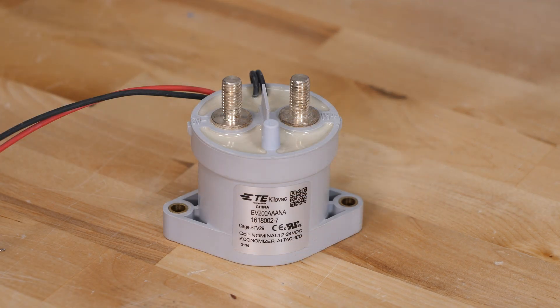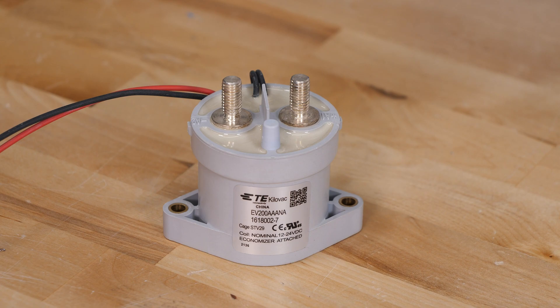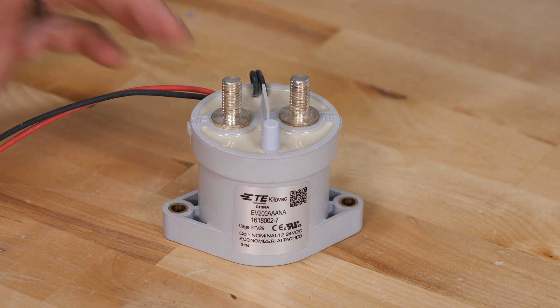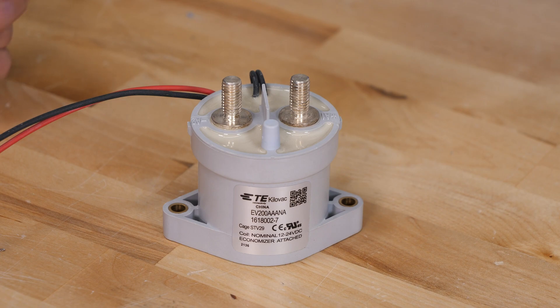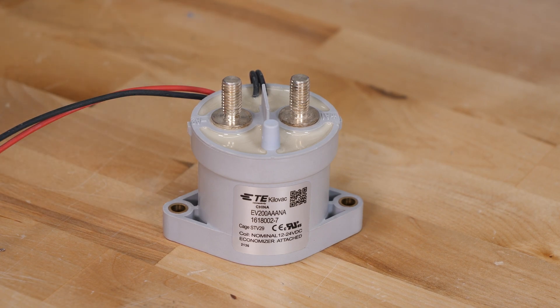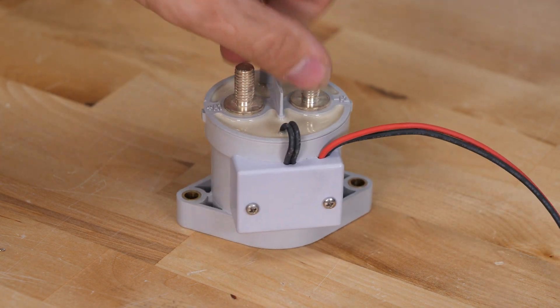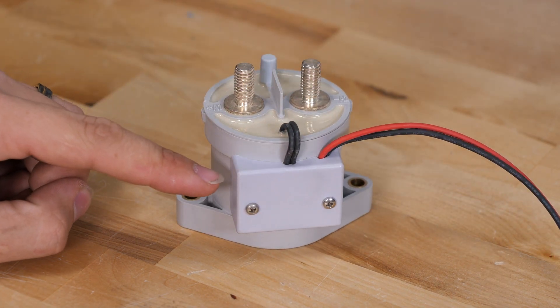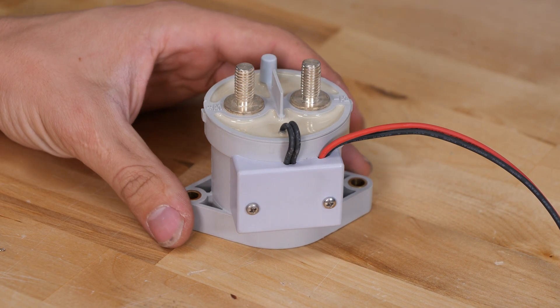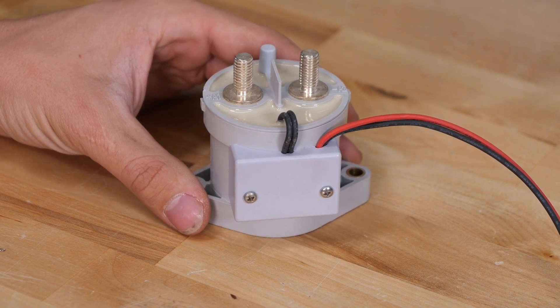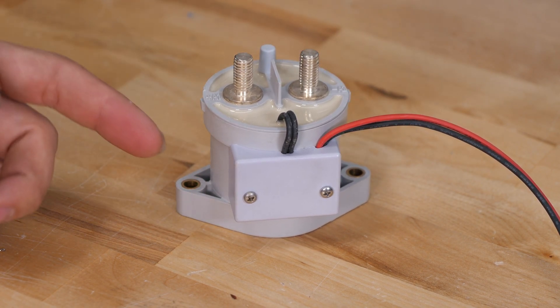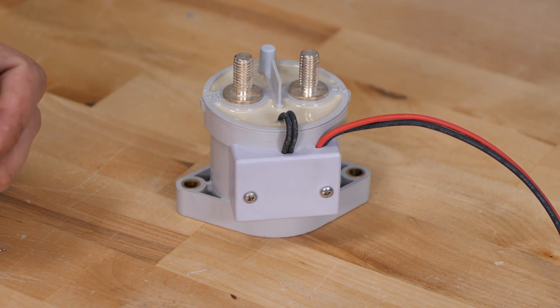This is a TE Connectivity Kilovac contactor. Now this is rated for 500 amps continuous current; however, you can even have a surge up to 2,000 amps and it can successfully break it. Now you're not going to get the best lifespan out of this, but if you did have an emergency situation, this contactor has got you covered. If I spin it around back, there is a block on here—you'll see this is an economizer circuit, which really helps reduce the current draw of this contactor once it's engaged. It drops that down quite a bit.